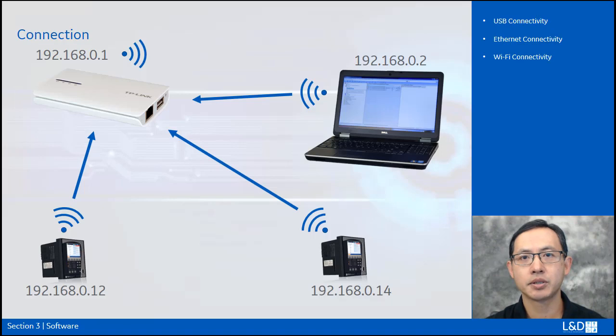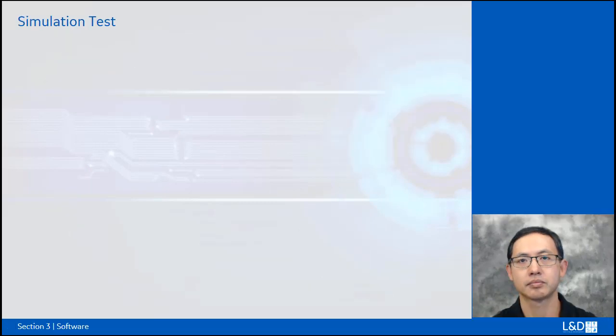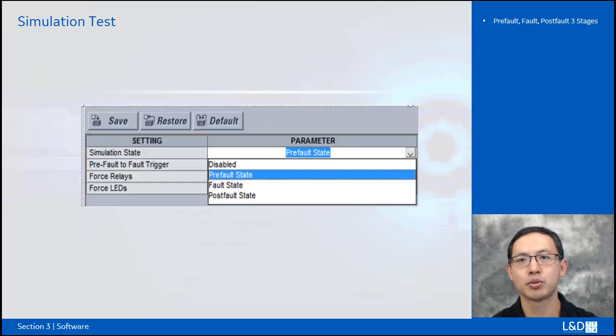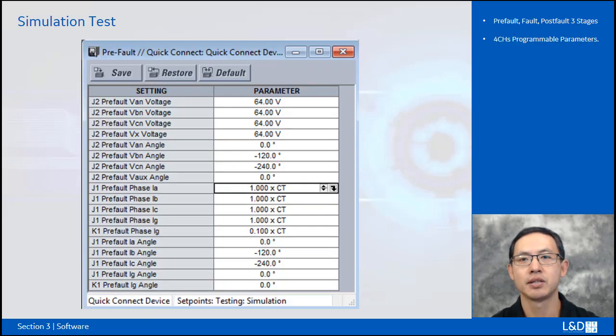8 series relay can be connected through USB connection and Ethernet connection, as with most multi-link relays. Its unique optional Wi-Fi connection simplifies setup and configuration, and diagnostic retrieval, with WPA-2 security. Simulation test can be programmed for pre-fault, fault, and post-fault 3 stages. For each stage, there are 4 channels. Programmable parameters can be programmed for the voltage and current. Depending on the configuration of the hardware, this could be like 8 CT and 8 VTs.